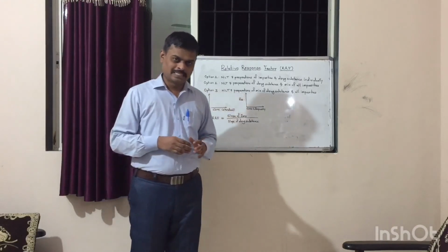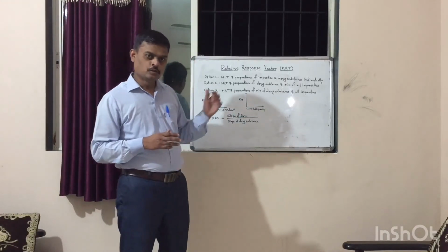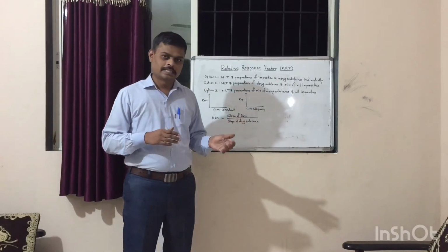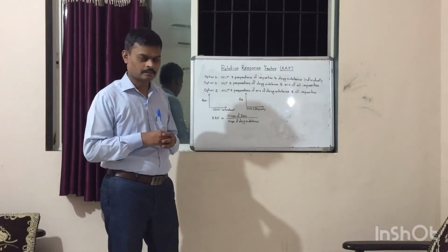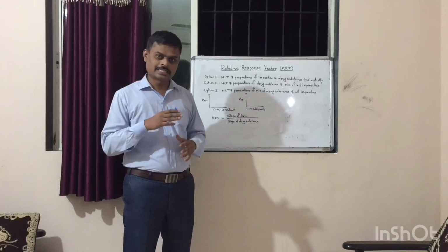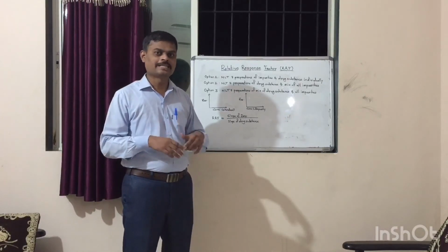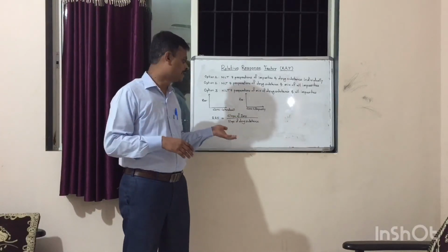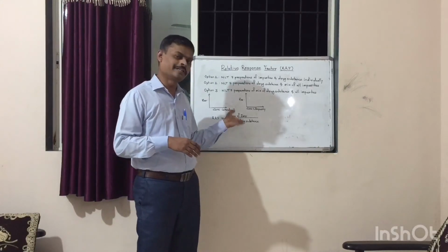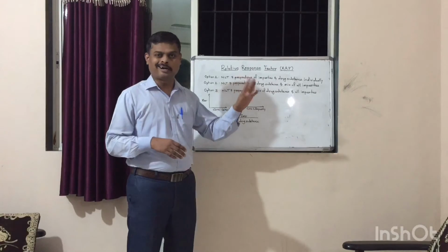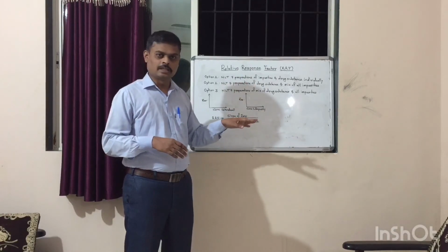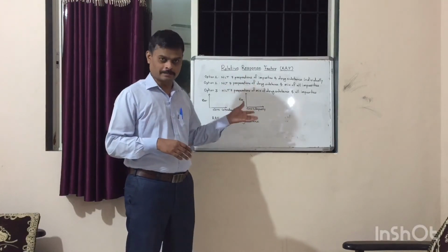However, while using RRF, some precautions need to be taken. RRF is sensitive to change in detector. If you switch over your detector, that is from UV to conductivity or UV to RI, your RRF will not remain the same.